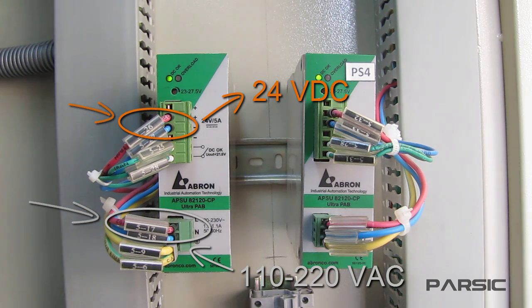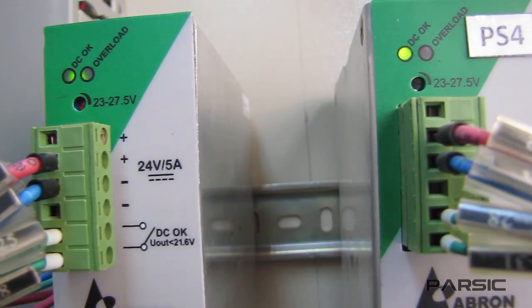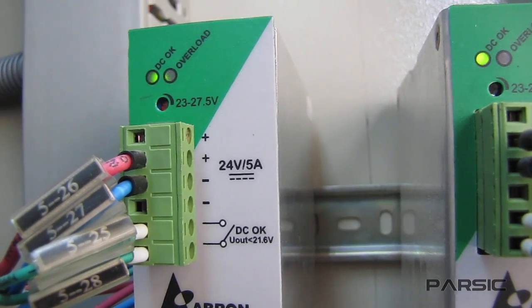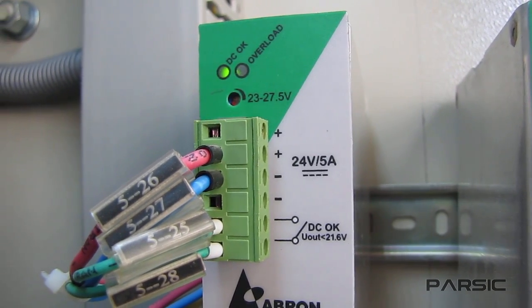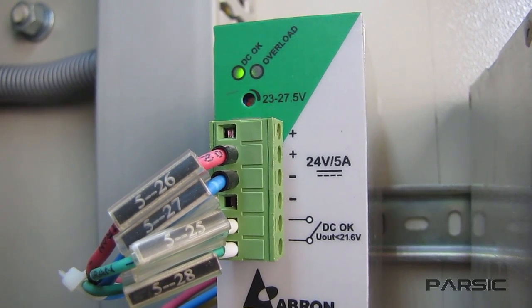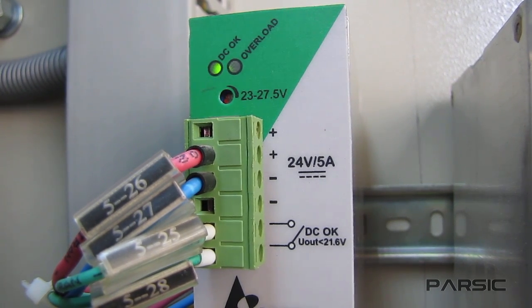In addition to the output voltage, another important parameter of power supplies is the current rating. The current rating of each of these power supplies is 5 amps, as you can see here. This shows the actual capacity of these power supplies — the maximum current that each of them can supply at the output is 5 amps. The more current the electrical devices within the enclosure draw, the higher the current rating of the power supply needs to be.